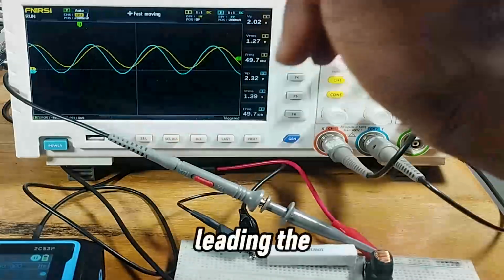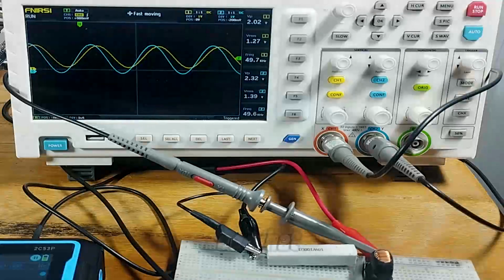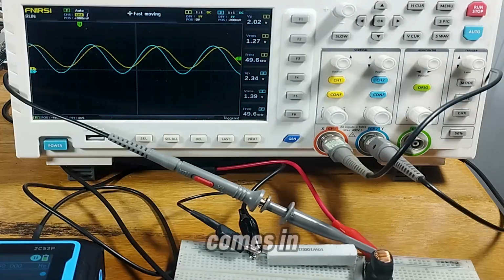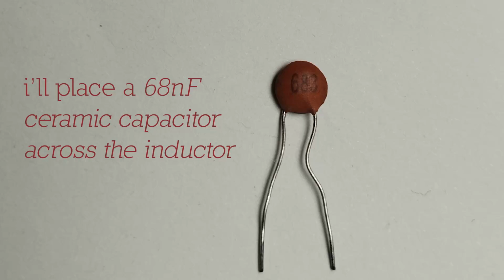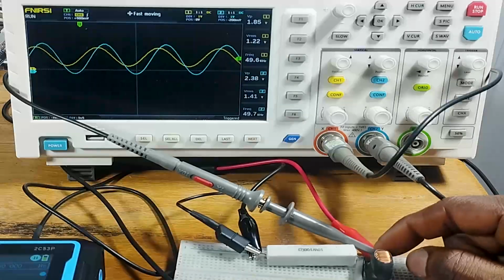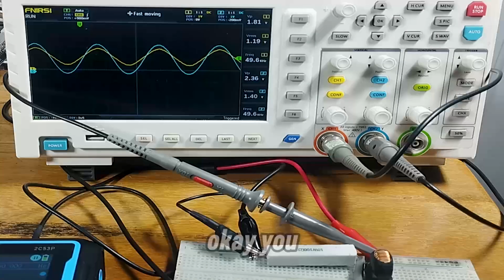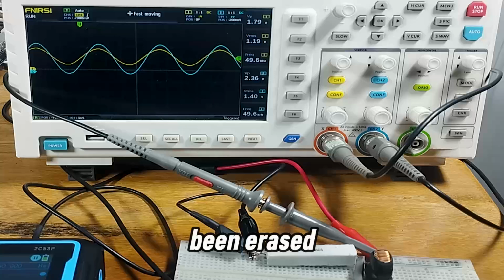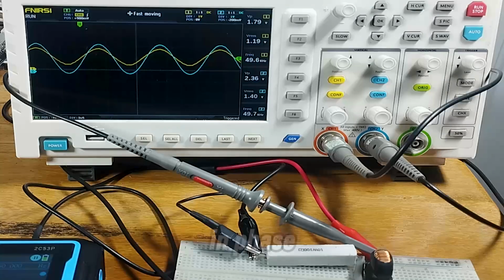Now we have the blue wave leading the yellow wave. So let's see what happens when the capacitor comes in. You see that has actually been erased. The wave now looks like it's in phase, right?